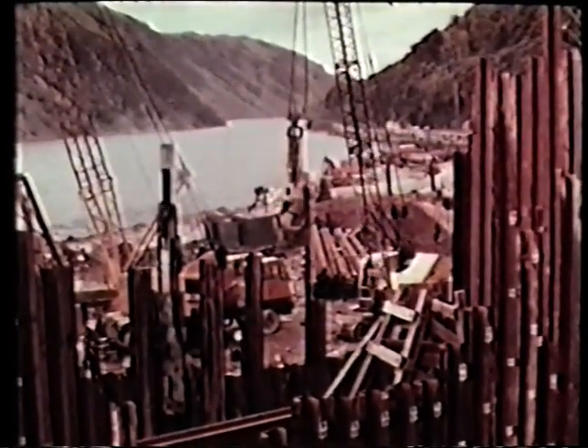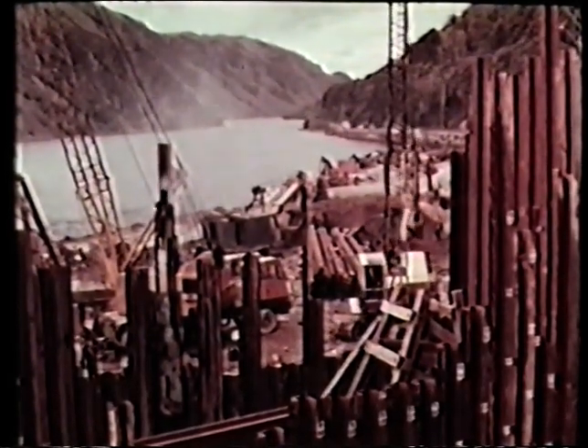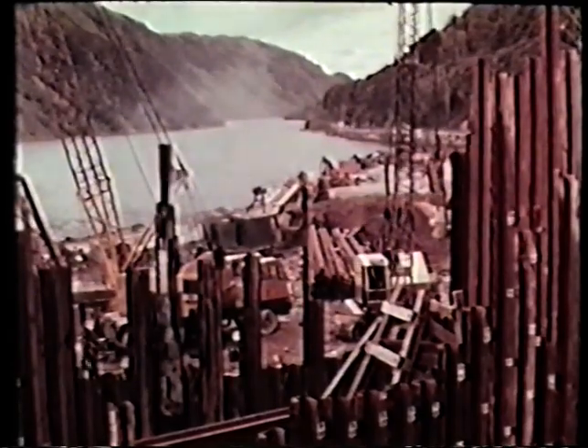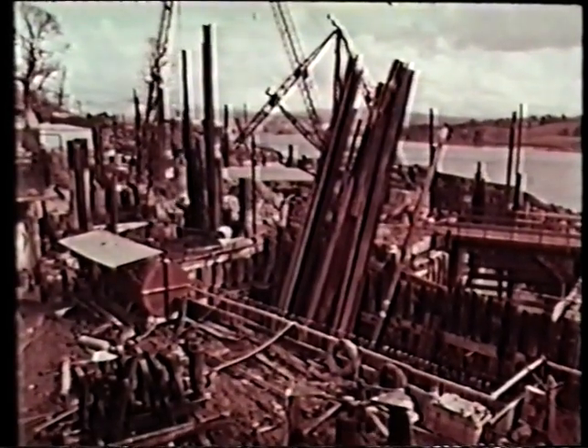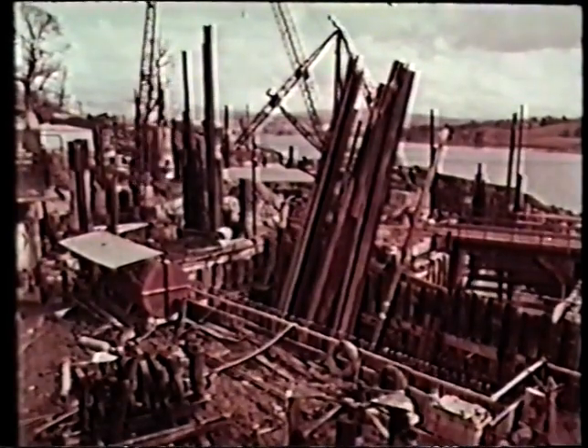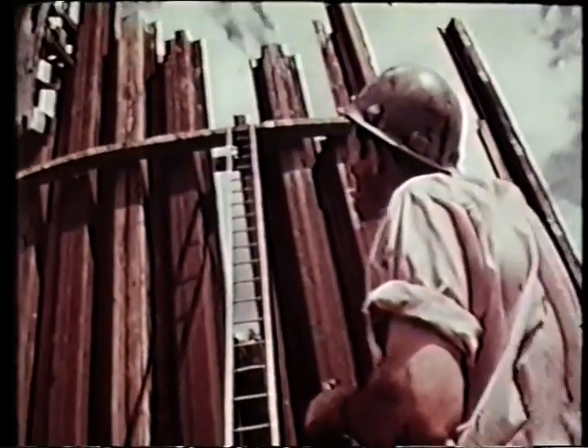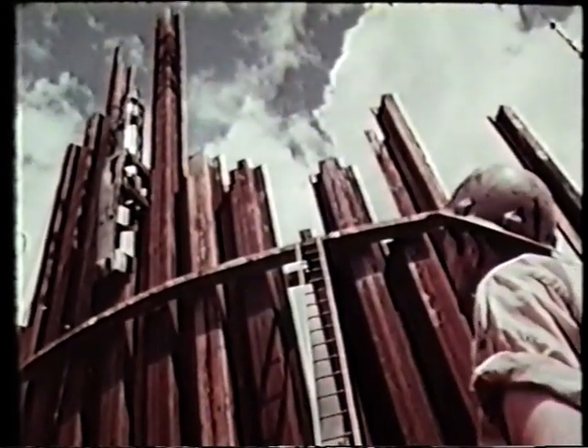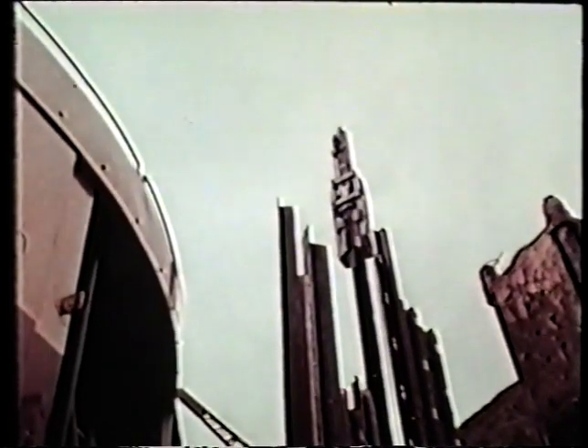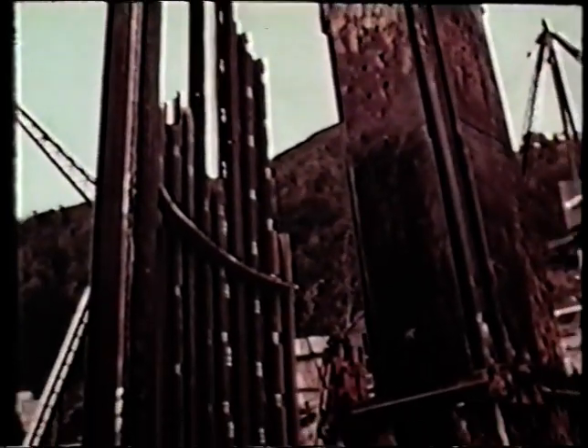Discharging over 8,000 tons of water a minute into Loch Awe and abstracting it again without injuring the fish meant an enormous outfall structure carrying 6,000 square feet of steel mesh screen to limit the velocity to not more than 1 foot a second. The fluctuation of water level of Loch Awe caused by the operation of the plant is only a few inches. Excavation and concreting of the four bay wing walls and screen supports was carried out inside the sheet steel piled cofferdams.